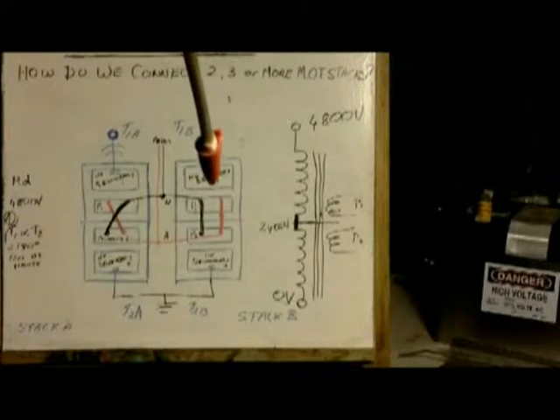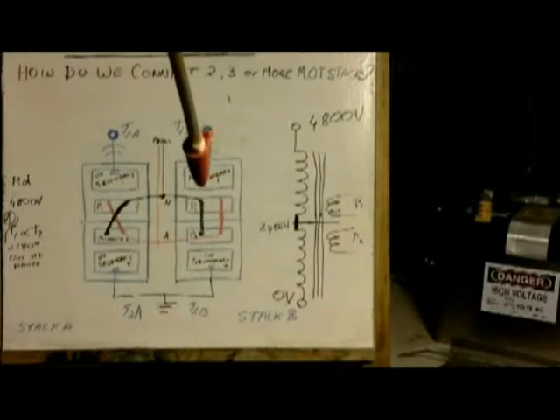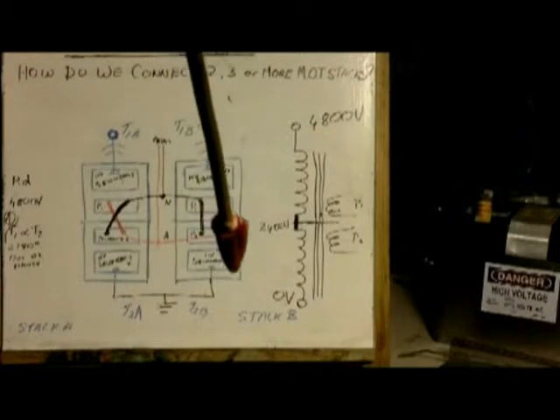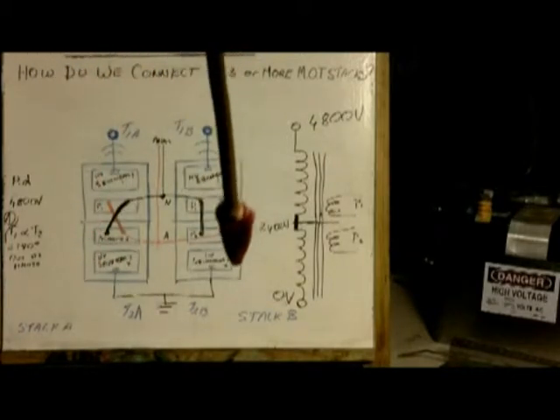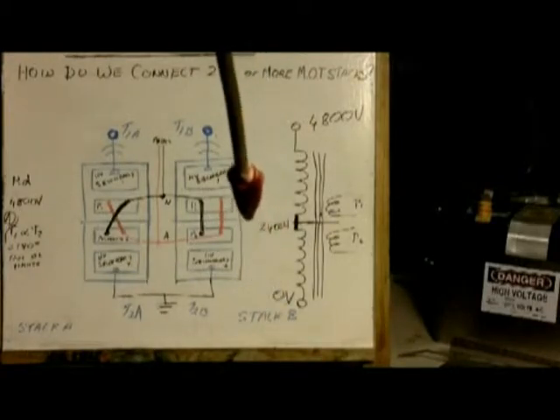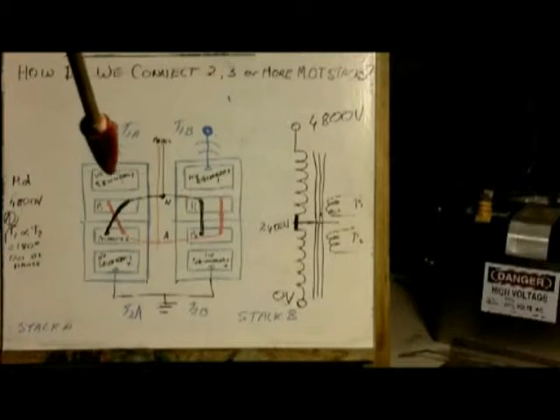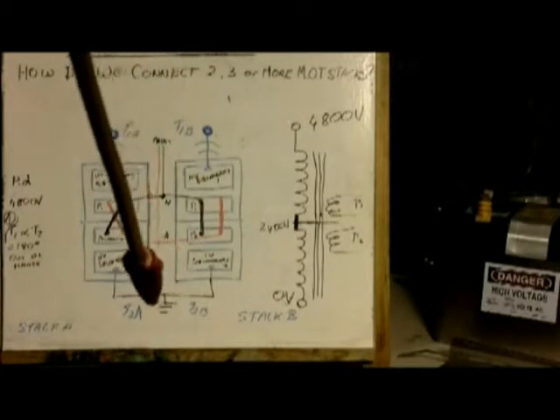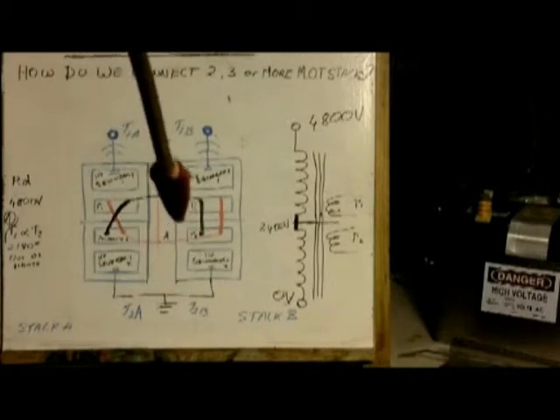There'll be a lot more stress between these 2 if the core was grounded. So it's not a bad arrangement. That's why I said it's not a bad arrangement. It's actually a fairly good one. The only difficulty is probably the type of enclosure that you're going to have to use, and that you're going to have to keep them isolated from the case, grounding only the terminals.